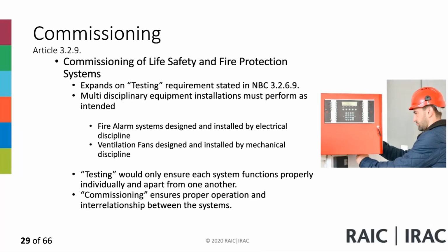We talked about 3.2.6.9 only for testing the systems for high-rise buildings. This goes beyond high-rise buildings. This applies to all buildings where we have fire protection and life safety systems installed. And it's not talking about just the commissioning requirements. It's talking about the integrated testing of all these systems to double check that they are properly integrated.